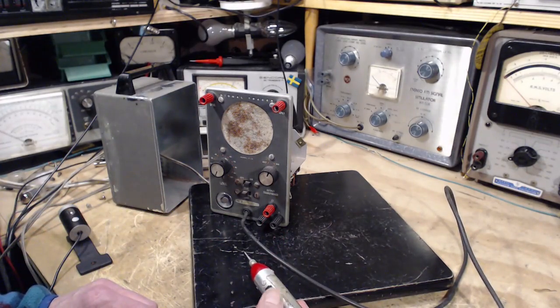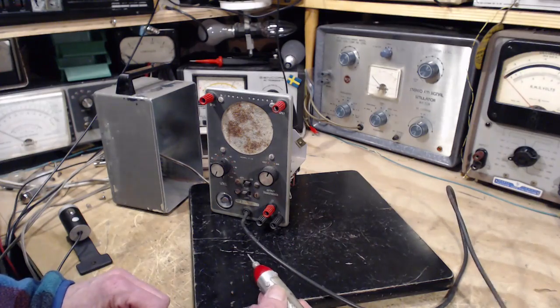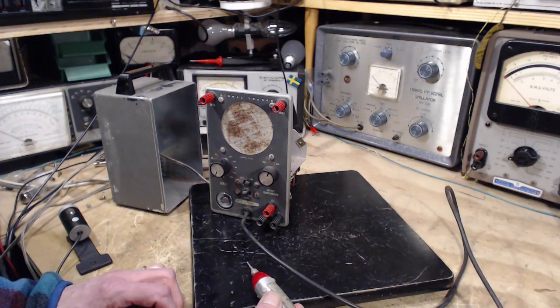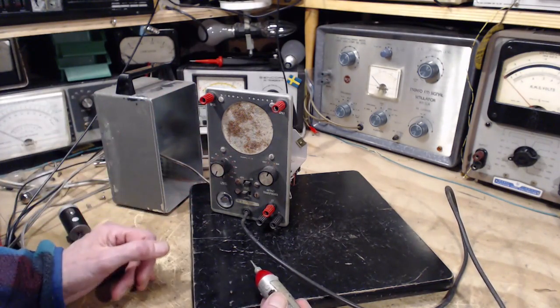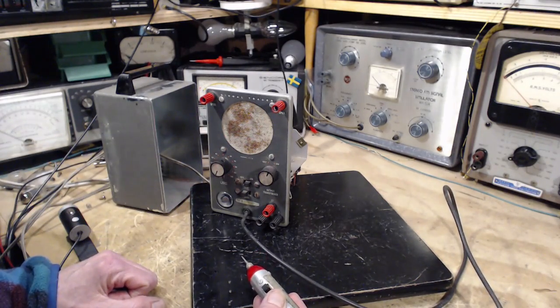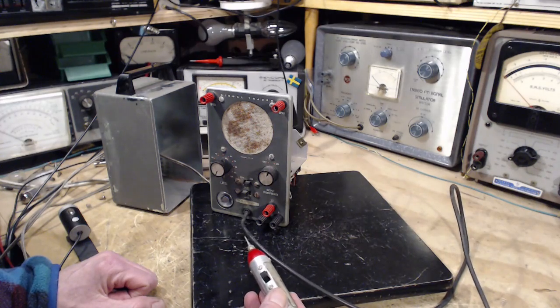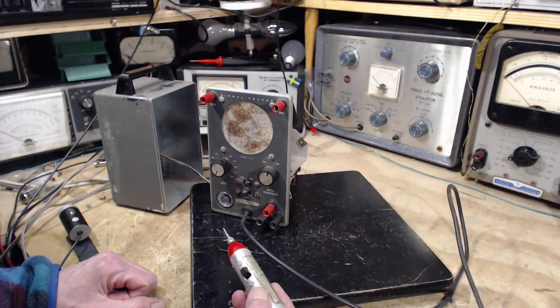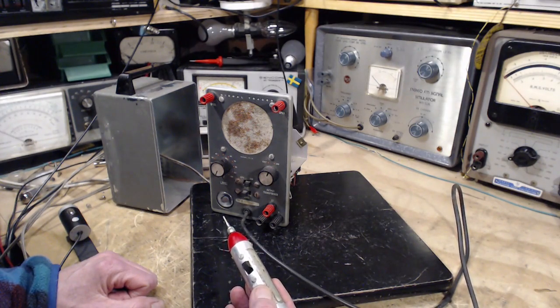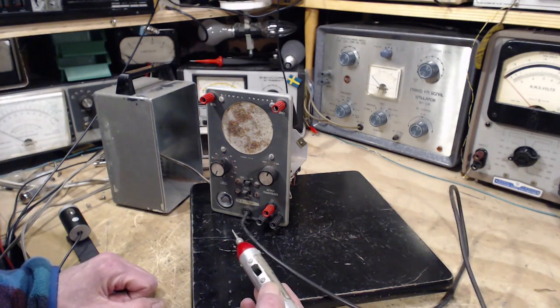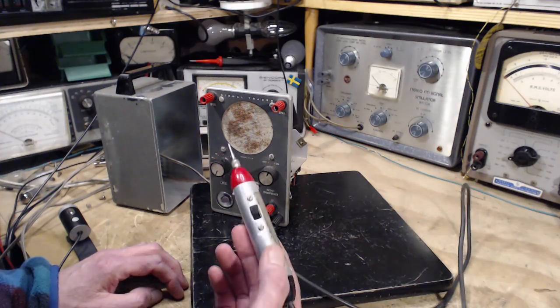And if the component has problems which might cause noise, basically loose connections, it should show up in the speaker, according to this. Very interesting. Never heard of anything quite like that. Never seen a testing device that, well, an ohm meter, but not like this, puts a voltage onto the device it's testing. That's very interesting.